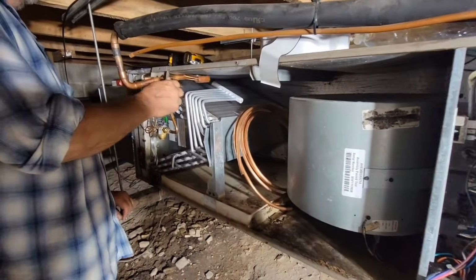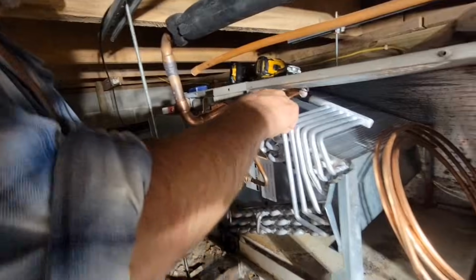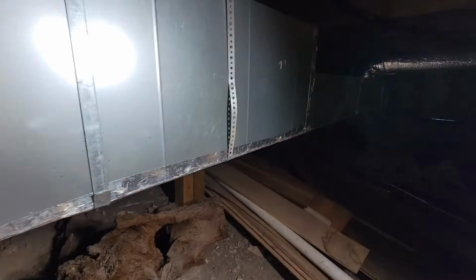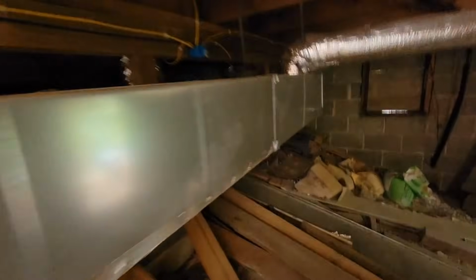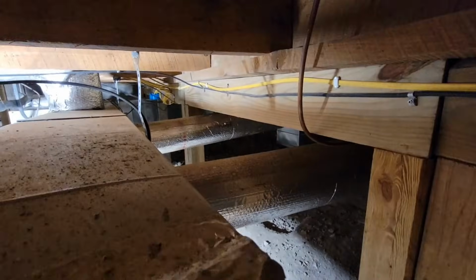Perfect. Willie's getting the copper installed. Looking good, Willie. And we got 2 different sizes. As far as how many vents we've got 1, 2, 3, 4, 5, 6, 7. So, and these are all the same size. It looks like all 6 inch. So we got 7 6-inch vents. That is totaling 700 CFM. So the first of the supplies will handle about 900 CFM. Total vents we have is about 700. Our unit will do about 800 CFM.